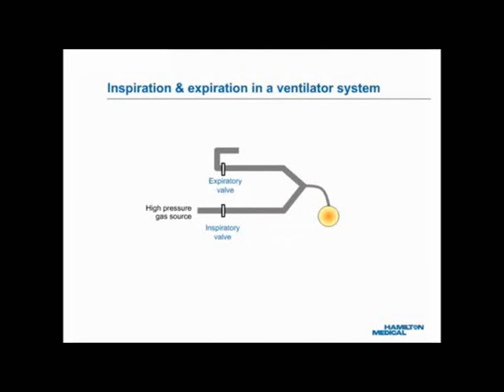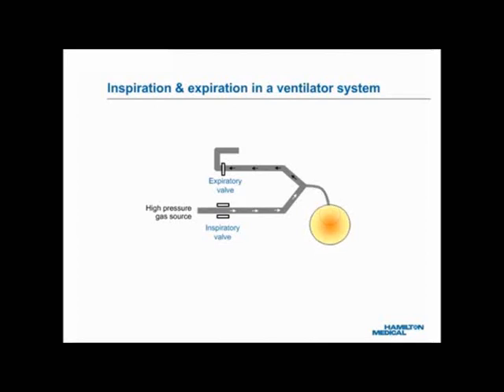In a real ventilator system, Hand A is replaced with an inspiratory valve and Hand B with an expiratory valve. On this slide, the circuit pressure is equivalent to airway opening pressure, or PAO, and the balloon pressure to alveolar pressure, or PALV. Balloon inflation: when the inspiratory valve opens and the expiratory valve closes, the circuit pressure becomes higher than the balloon pressure, and gas is pushed into the balloon — as a result, the balloon grows. Balloon deflation: when the inspiratory valve closes and the expiratory valve opens to the environment, the circuit pressure drops below the balloon pressure, and gas is pushed out of the balloon — as a result, the balloon shrinks. Valve control in a real ventilator system is more complicated than this, but the basic principle remains valid.